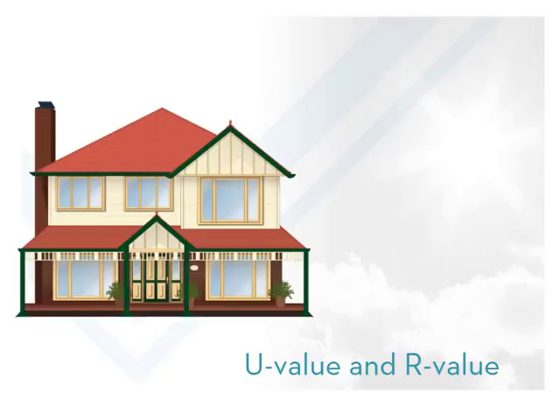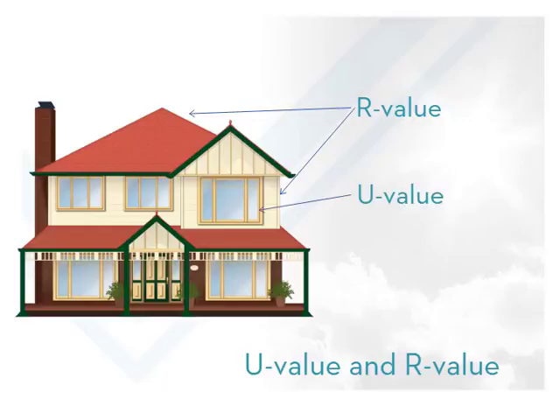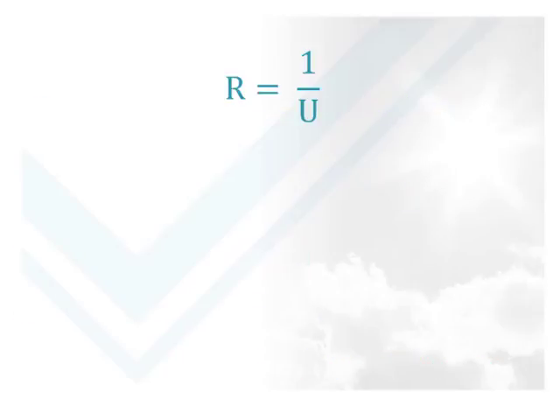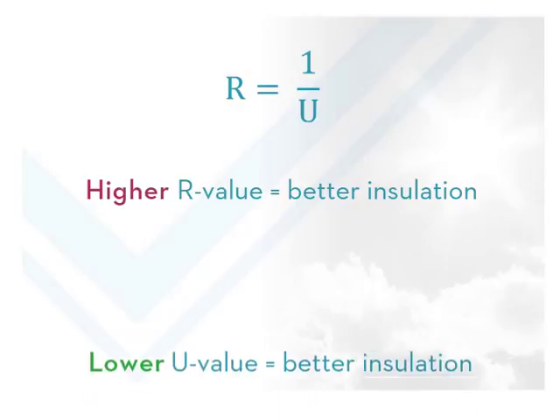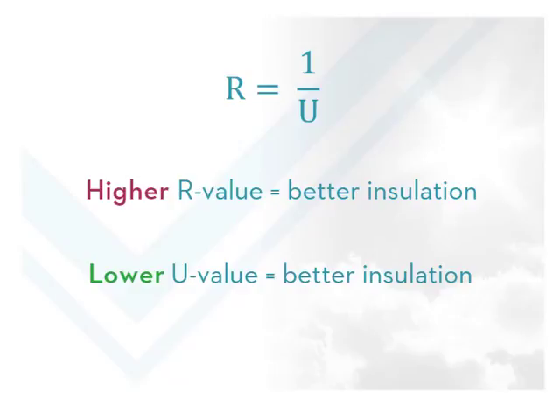U-value and R-value shouldn't be confused with one another, as they're essentially two sides of the same coin. R-value is cited when discussing things such as wall and ceiling insulation values, but it doesn't translate well to windows and other fenestration products, so Australia uses the international protocol of U-values for regulation. The two are inversely related: the higher the R-value, the better insulated the walls and ceilings are; the lower the U-value, the better job a window does in keeping out the heat and cold. It's vital that during the design-build stage, building designers, specifiers and energy assessors consider the benefits window products with lower U-values confer on the overall energy efficiency of a building.